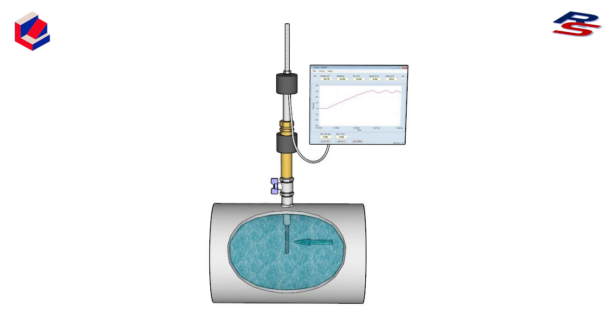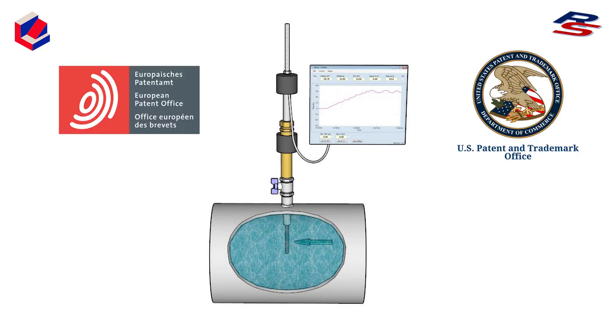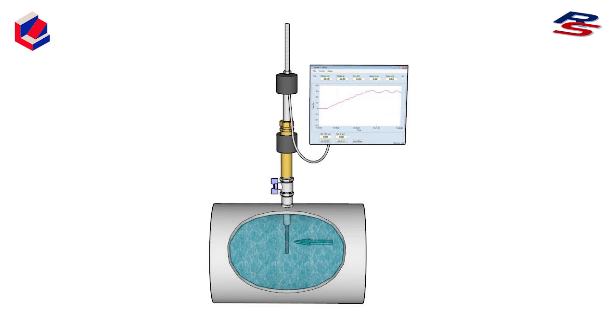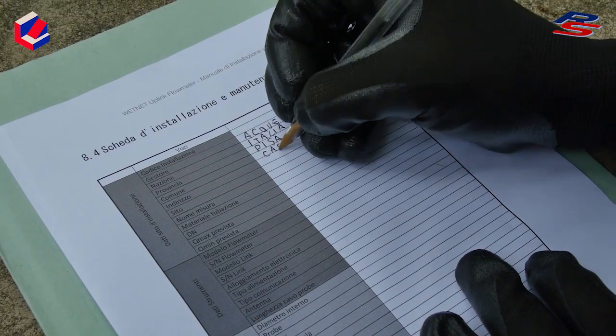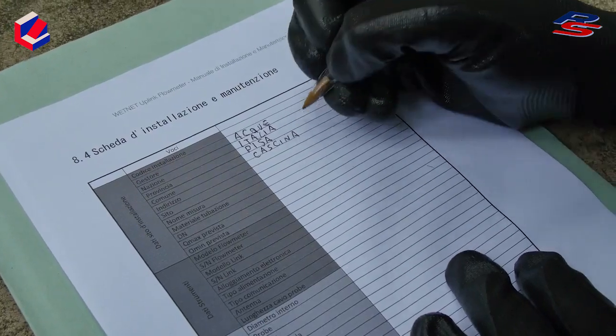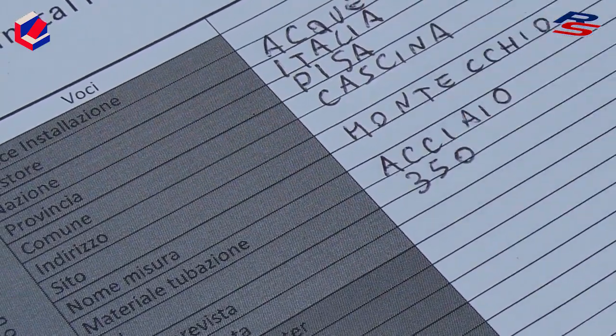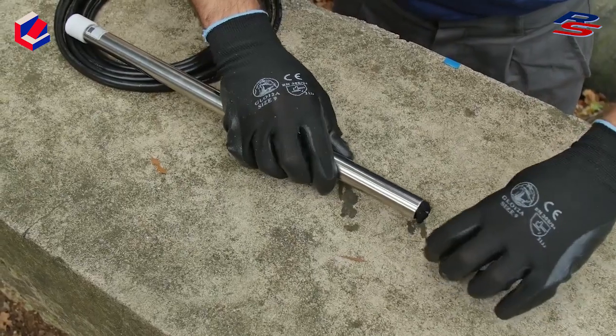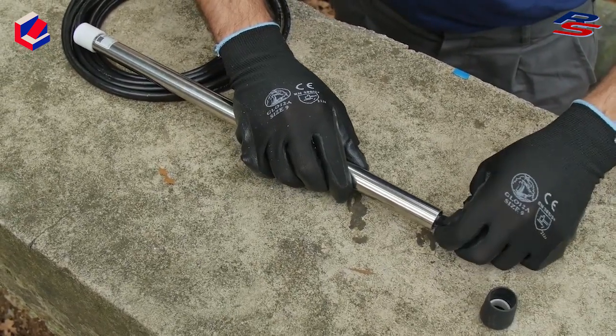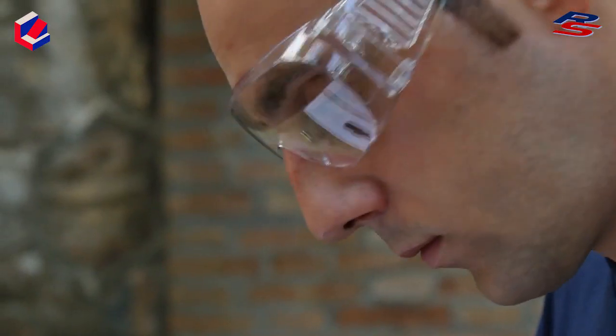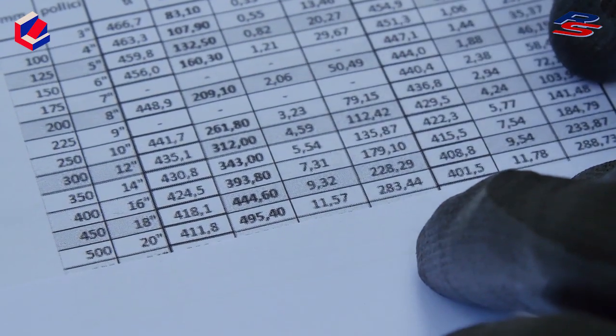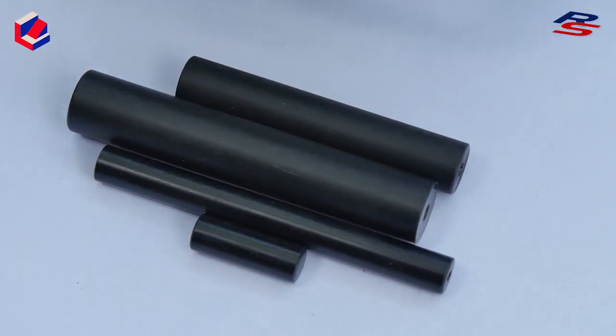The Resotech flowmeter bases its action on a patented innovative method which is used to measure hydraulic pressure. The force exercised by the water is read by a metering cylinder installed on the sensor, which is fitted inside the pipeline. Installing the sensor is a very simple operation and can be done without interrupting the flow. Installation of the device requires the application of a jack on which a special inserter is screwed.